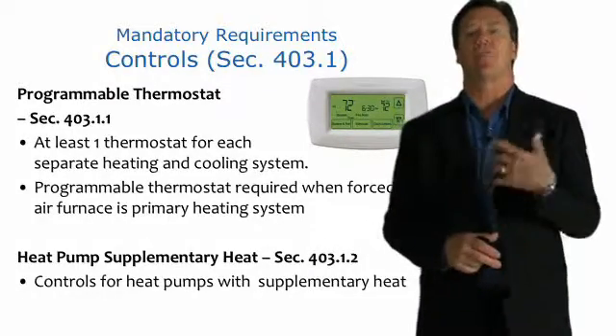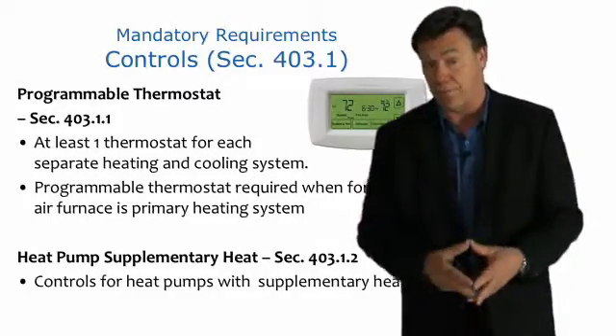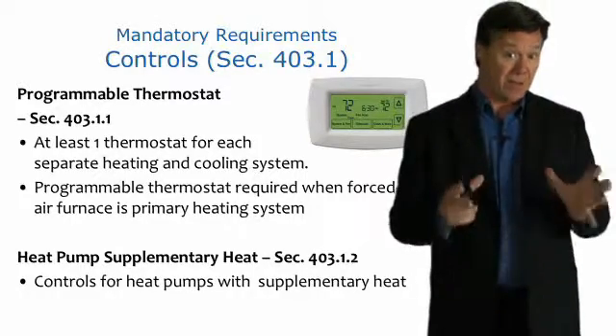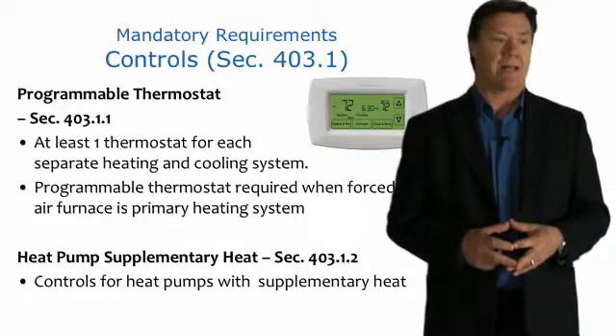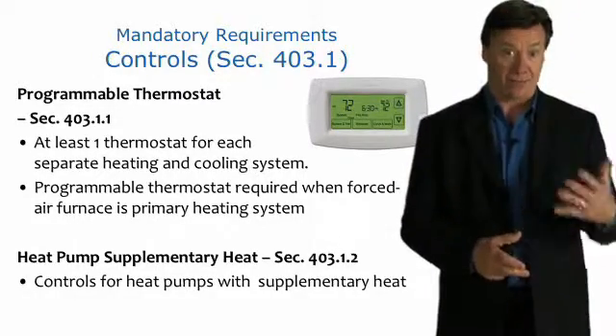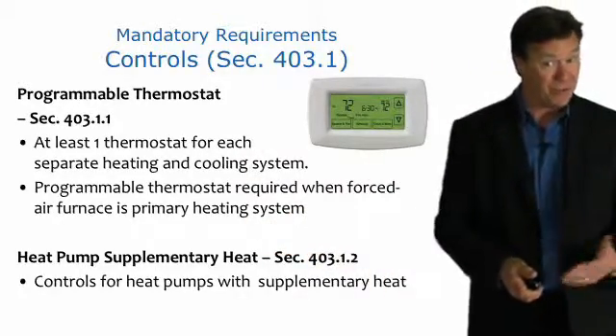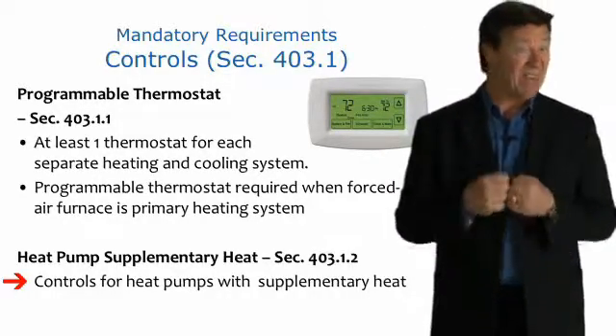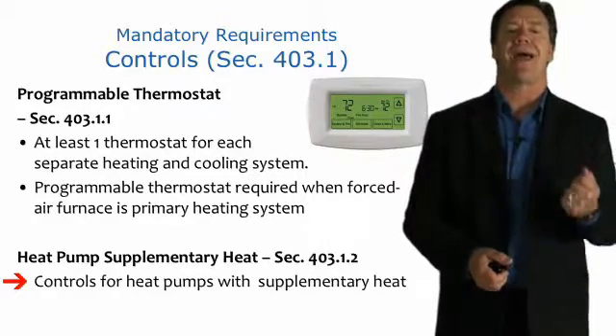Typically, heat pumps have supplementary heat. There are two basic forms: a natural gas or fossil fuel fired furnace, or most commonly an electric furnace backup. These electric furnaces have electric elements called heat strips, which can be as much as 10 kW of electricity usage — like a giant toaster. When these electric strips heat up, they meet the demand for heating, but it's not efficient and it's very expensive. The code requires heat pumps to have controls so that the strips won't kick on until absolutely necessary.